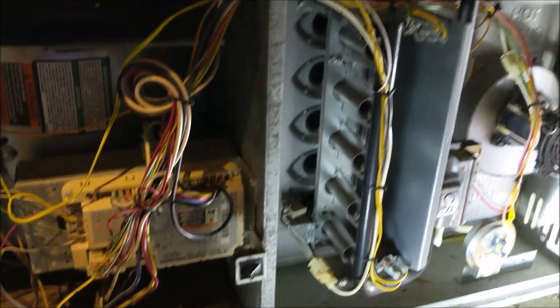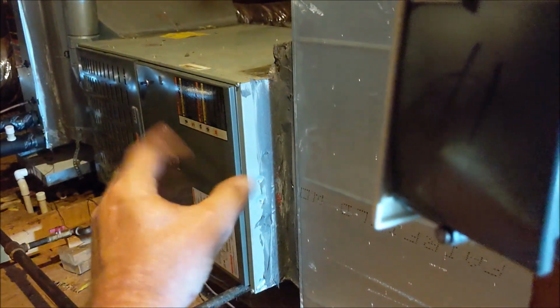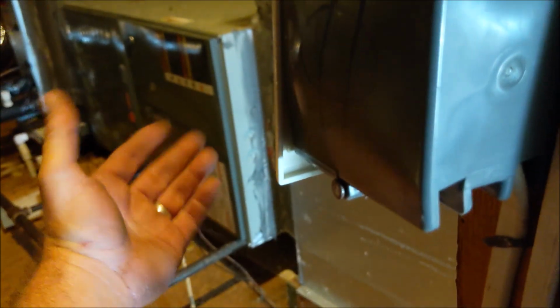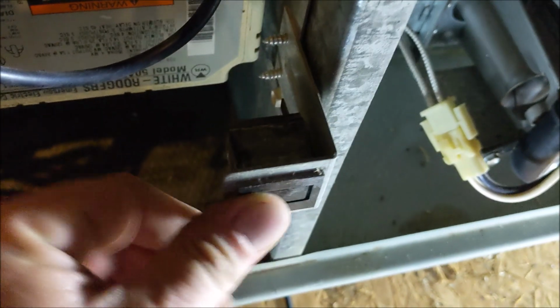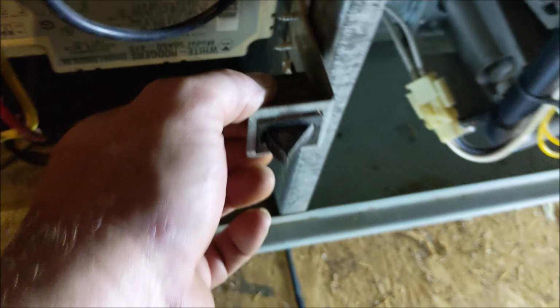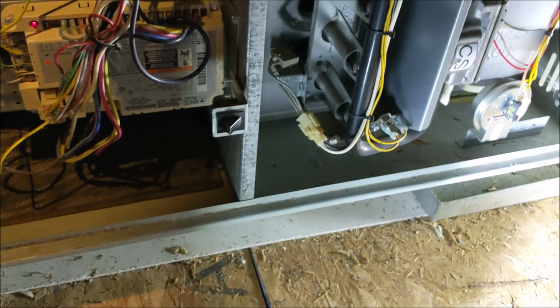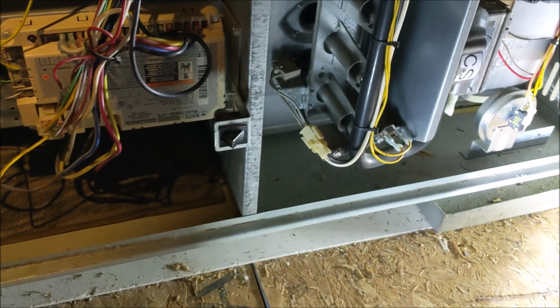So upstairs we have two gas furnaces sharing the same air return. This one is the variable speed newer model, and when you open up the door the blower shuts down. This one here, as you can see, the safety switch is not connected, don't even have any wires to it, so when you open up the door it should shut the motor off. We do recommend installing it for safety.